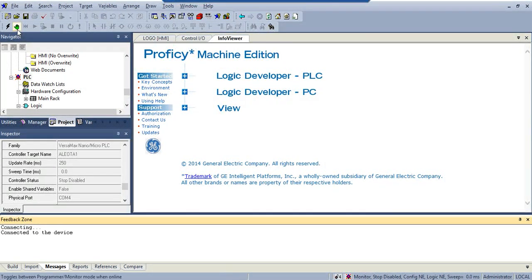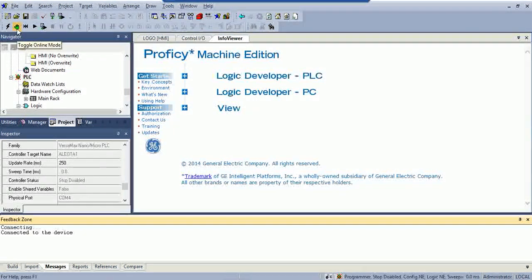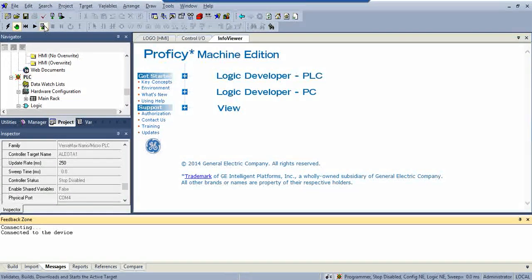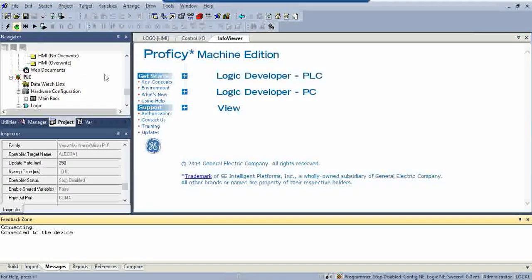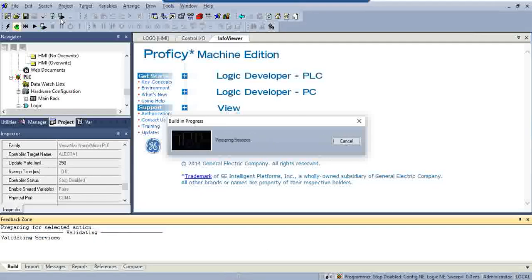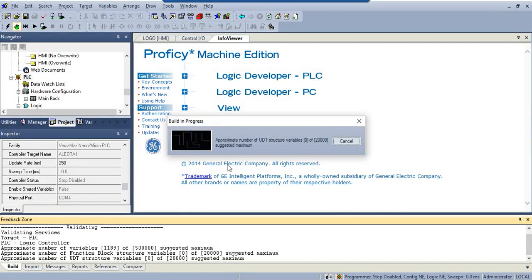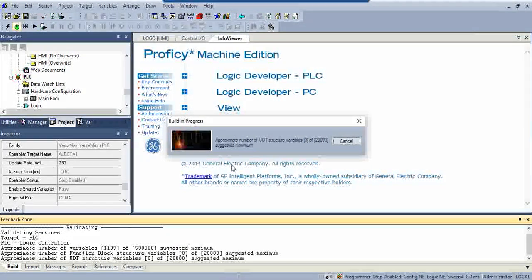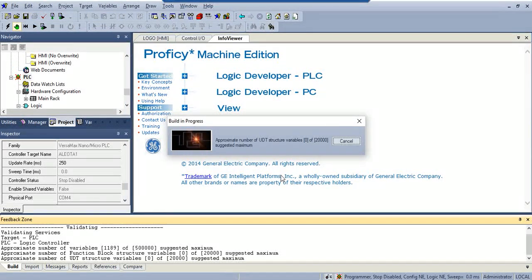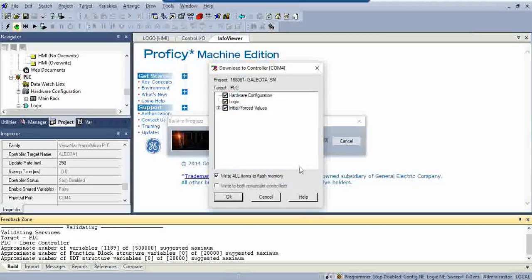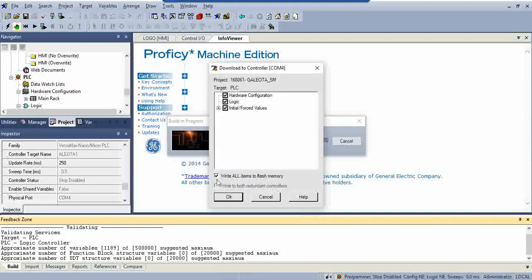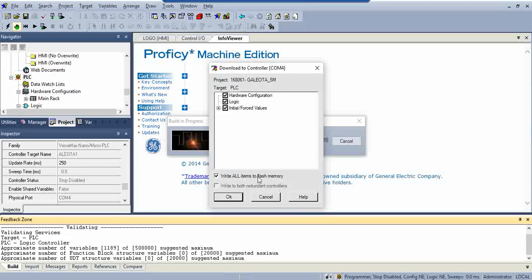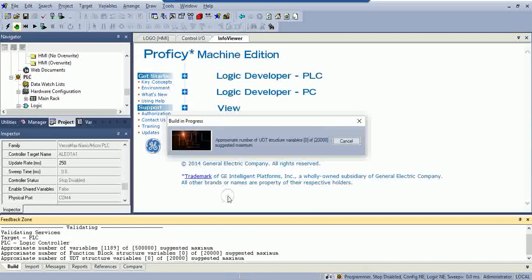Now, you hit the green hand to go online, and right now it's asking me if I want to download. So, I'm going to go ahead and hit download. Now, make sure you tick, write all items to flash memory, and then hit OK.